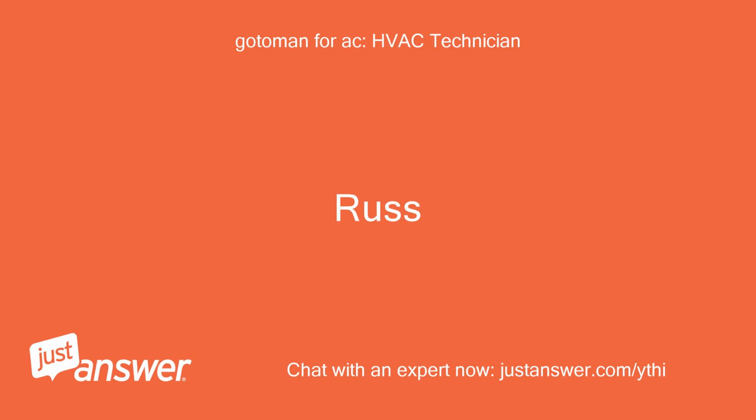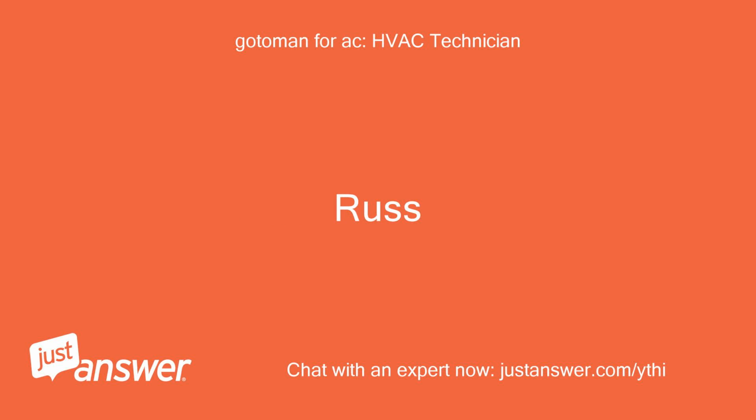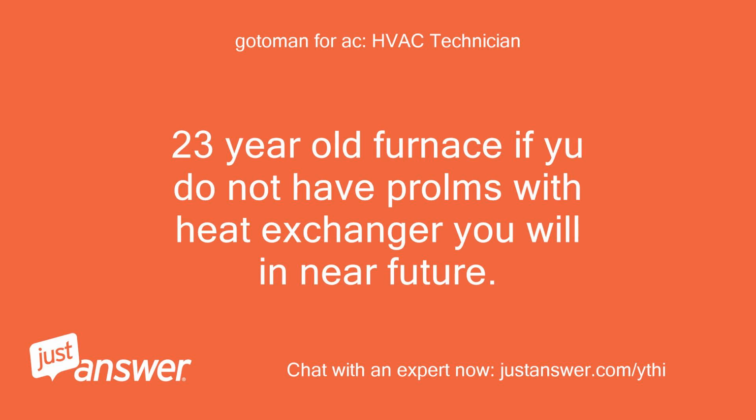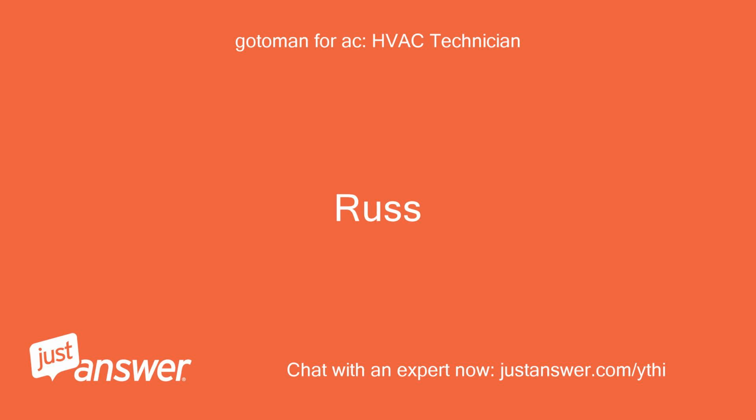Russ. Any more questions? Russ. Flue pipe is about average $20 per foot. With a 23-year-old furnace, if you do not have problems with the heat exchanger, you will in the near future. The new 90% furnace uses PVC as the vent, not Type B venting. Russ.